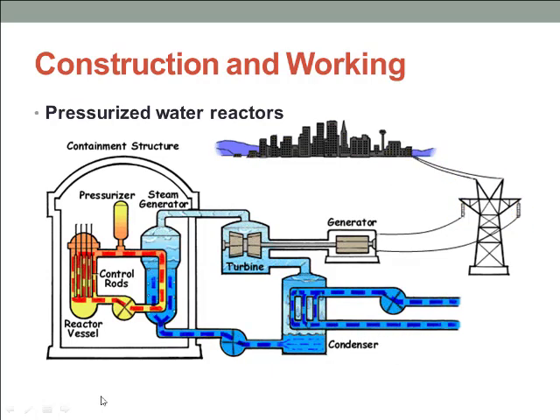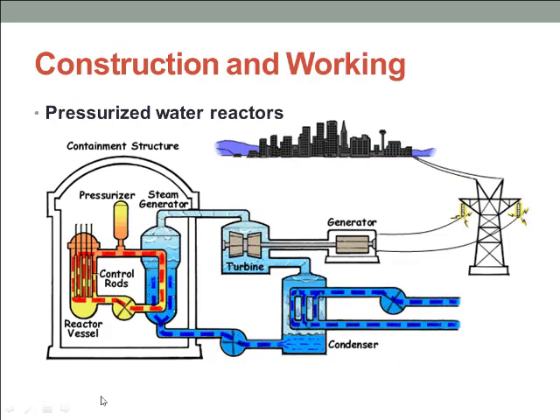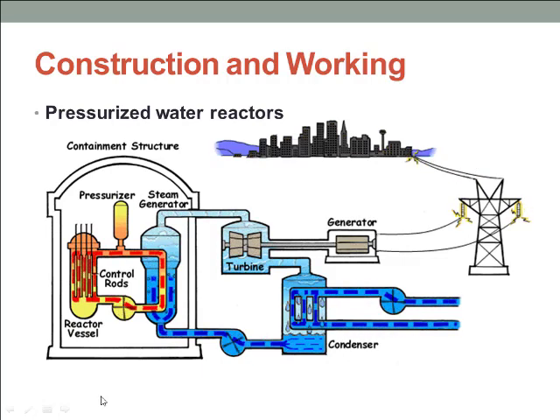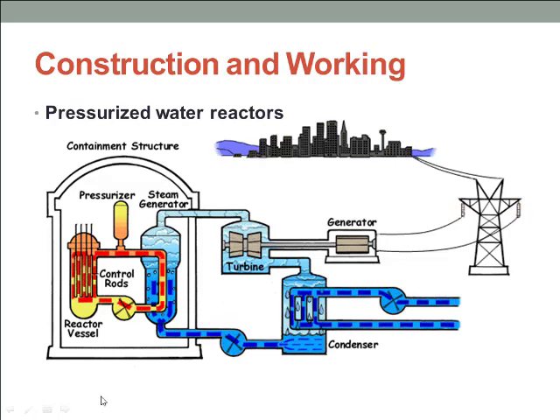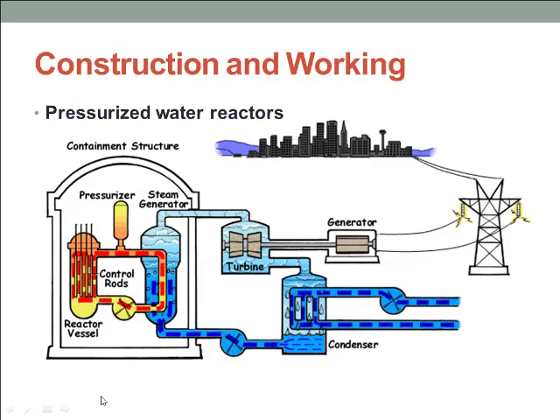Water in the reactor core reaches about 325 degrees Celsius, hence it must be kept under about 150 times atmospheric pressure to prevent it from boiling. Pressure is maintained by steam in a pressurizer in the primary cooling circuit. The water is also used as a moderator, but if any of the water turns into steam the fission reaction will be slowed down, so higher pressure must be maintained in the pressure chamber to keep the water in liquid form.